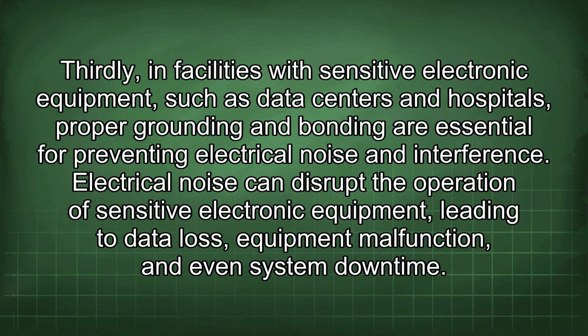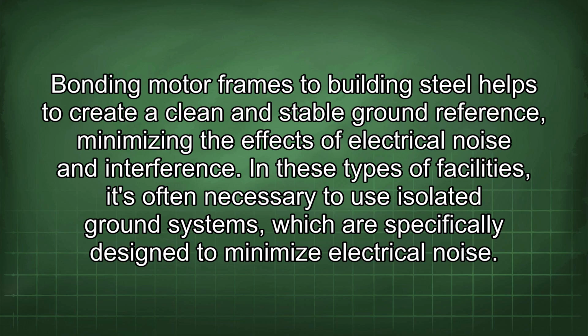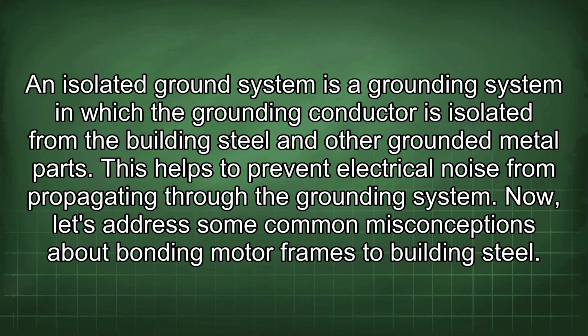Thirdly, in facilities with sensitive electronic equipment, such as data centers and hospitals, proper grounding and bonding are essential for preventing electrical noise and interference. Electrical noise can disrupt the operation of sensitive electronic equipment, leading to data loss, equipment malfunction, and even system downtime. Bonding motor frames to building steel helps to create a clean and stable ground reference, minimizing the effects of electrical noise and interference. In these types of facilities, it's often necessary to use isolated ground systems, which are specifically designed to minimize electrical noise. An isolated ground system is a grounding system in which the grounding conductor is isolated from the building steel and other grounded metal parts. This helps to prevent electrical noise from propagating through the grounding system.